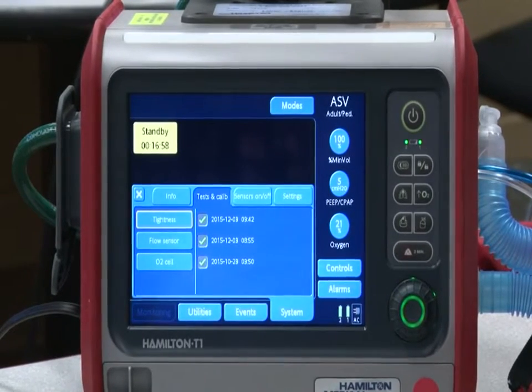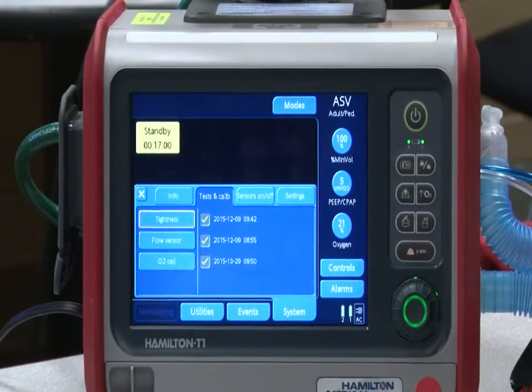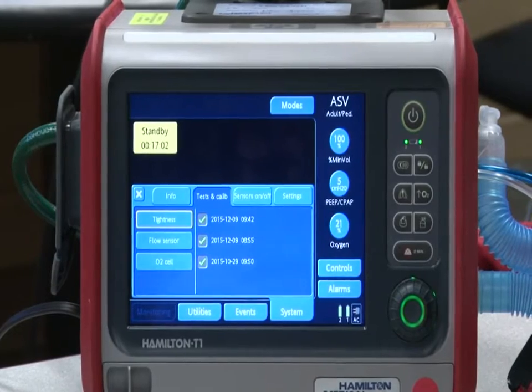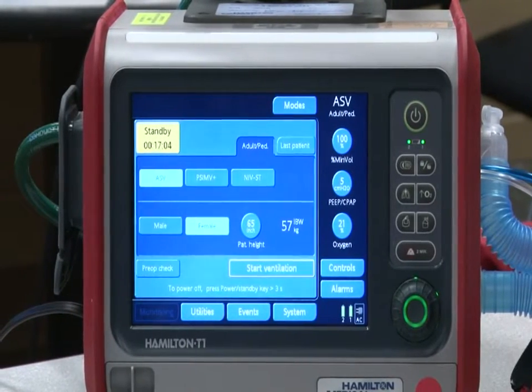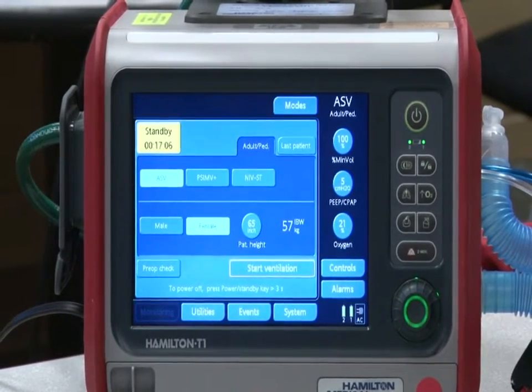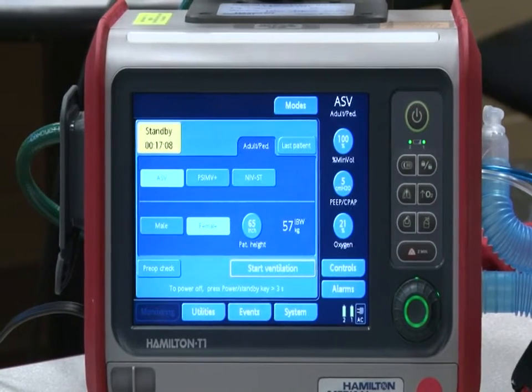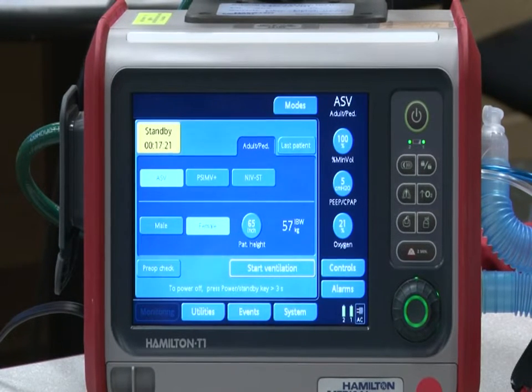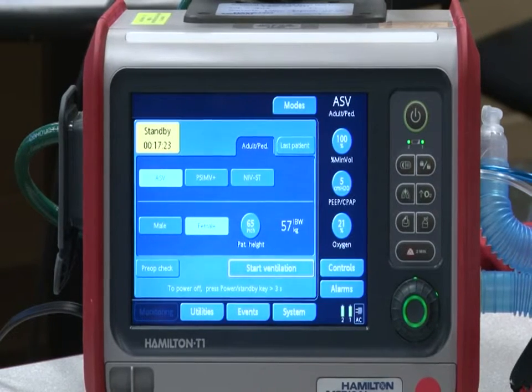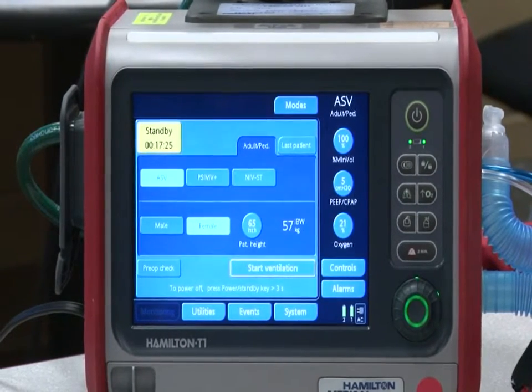Okay. Put that airway adapter on, now the calibration adapter, and then hit the flow sensor test and just read under the time bar. First it's going to check, you have to start with it open to room air. For both tests, you have to start with it open to room air. So go ahead and hit the flow sensor calibration and read under the little time bar and it'll tell you what to do. So when it says turn the flow sensor, pull the adapter and the flow sensor off and put it on backwards. Or if you started with it backwards, that's okay too.